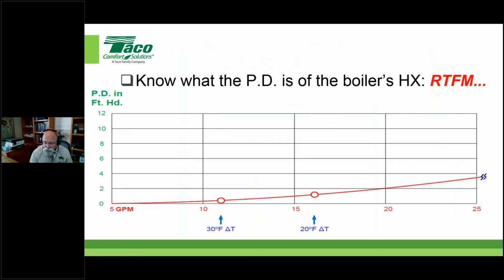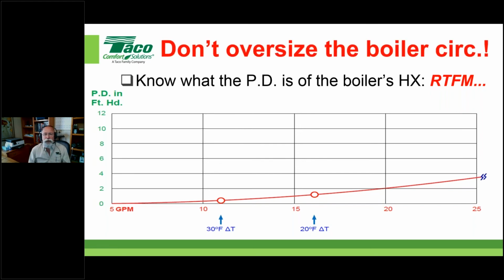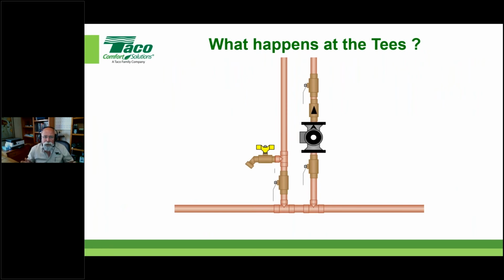And you folks know kind of where I'm going with this one, especially how I ended it there. You have to read the manual, and the manual is what will tell you what to expect as far as pressure drop is concerned from the boiler's heat exchanger. Okay, and I can't overemphasize this. Don't oversize the boiler circulator in a primary secondary application. It's not good for anybody.